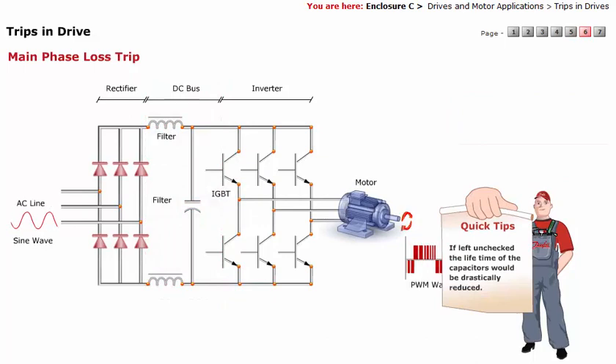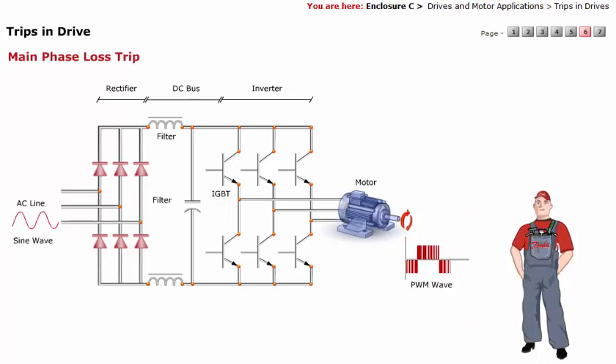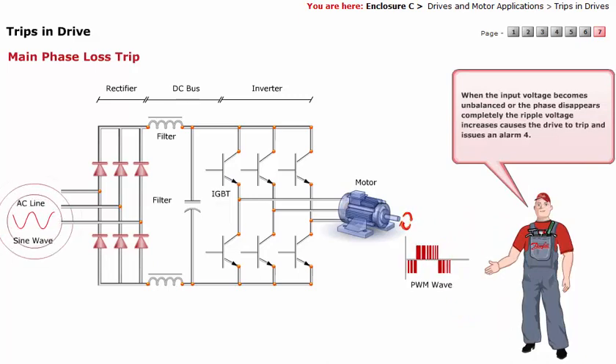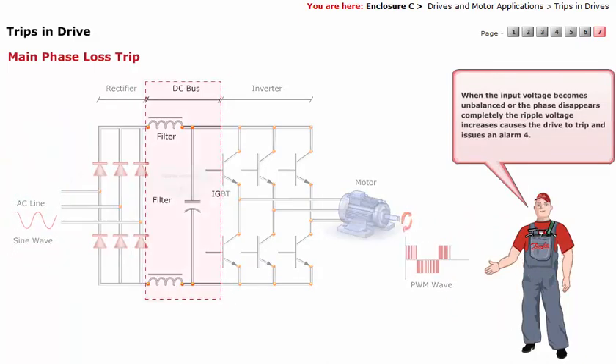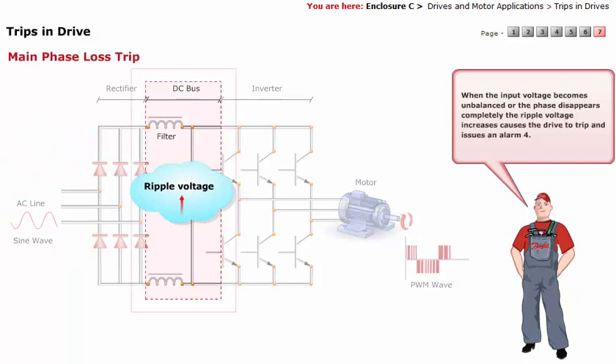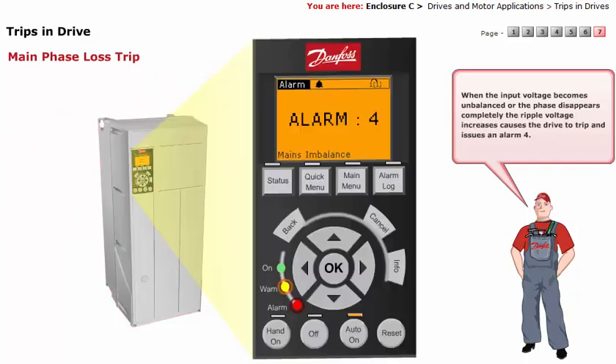If left unchecked, the lifetime of the capacitors would be drastically reduced. The phase loss will only be detected if the load is larger than about 30 to 40% of full output load of the drive. When the input voltage becomes unbalanced or the phase disappears completely, the ripple voltage increases, causing the drive to trip and issue an alarm.